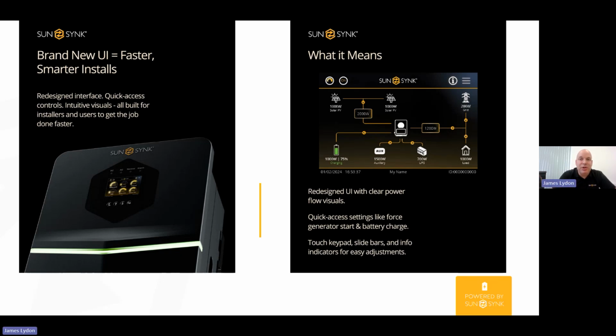Okay, so on the Acure, we've got our brand new user interface. It's sleeker. We've completely redesigned it. We've taken feedback from installers. We've introduced sort of quick access controls. And then on the right-hand side image, you can see the power flow. So it will show you what both strings are generating, obviously what's coming in from the grid, your load. If you're using that backup load, the UPS load, because when on grid, that UPS load is powered also. So if, let's say there's no PV being generated and the batteries are at a low SOC, that UPS load is still powered from the grid as a pass-through. It's also showing you what your auxiliary load is doing.